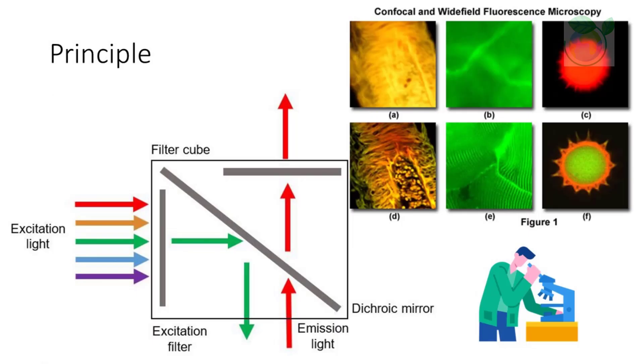However, as much of the light from sample fluorescence is blocked at the pinhole, this increased resolution is at the cost of decreased signal intensity, so long exposures are often required. As only one point in the sample is illuminated at a time, 2D or 3D imaging requires scanning over a regular raster in the specimen. The thin optical sectioning capabilities make these types of microscopes particularly good at 3D imaging and surface profiling of samples.